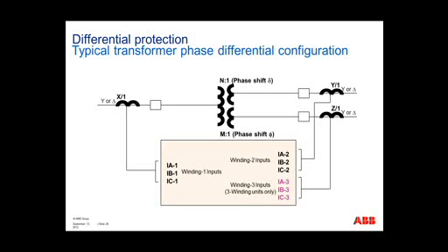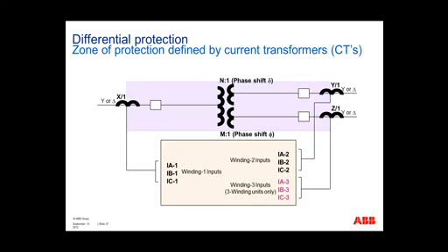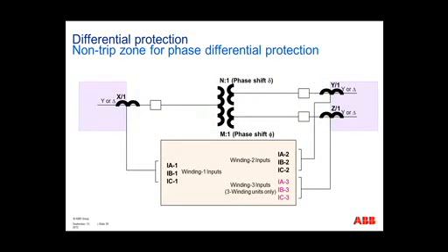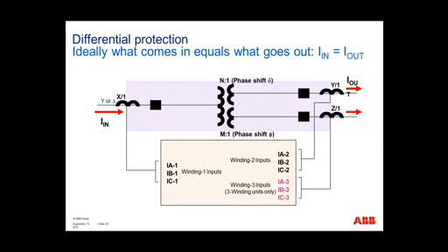Now our zones of protection, and what area of the transformer we want to protect when we talk about our transformer differential protection. Shown in blue is the zone of protection that we're going to concentrate on, and that's dictated to us by the position of the CTs. We desire these CTs to be outside the breakers, so the breaker is included in the zone of protection. So for the part shaded in blue, we would need instantaneous tripping anytime a fault occurs in that zone. Outside the zone of protection, what's shaded now is where we need restraint. So our differential protection provides us this restraint on these areas outside our zones of protection.